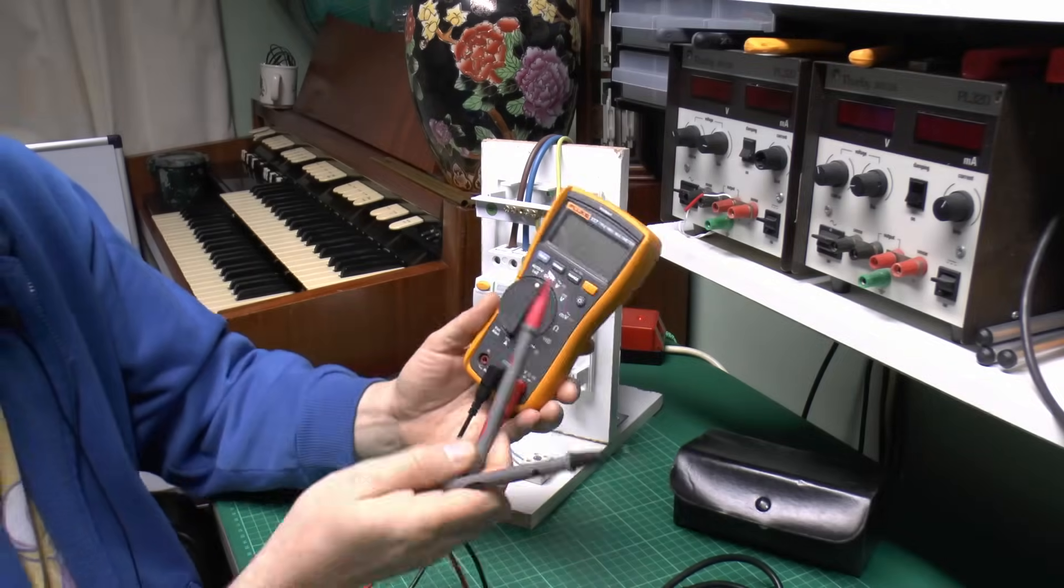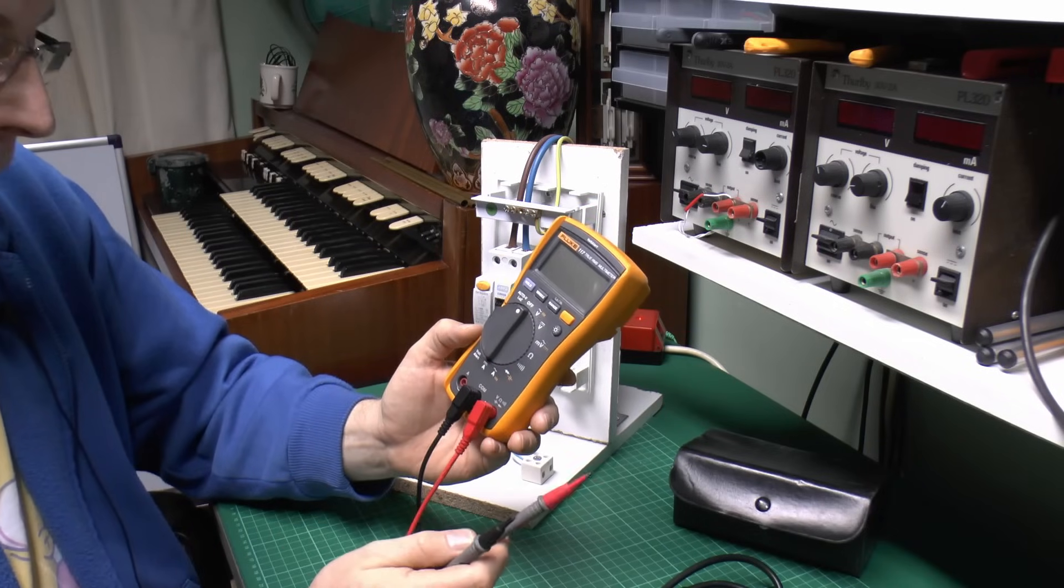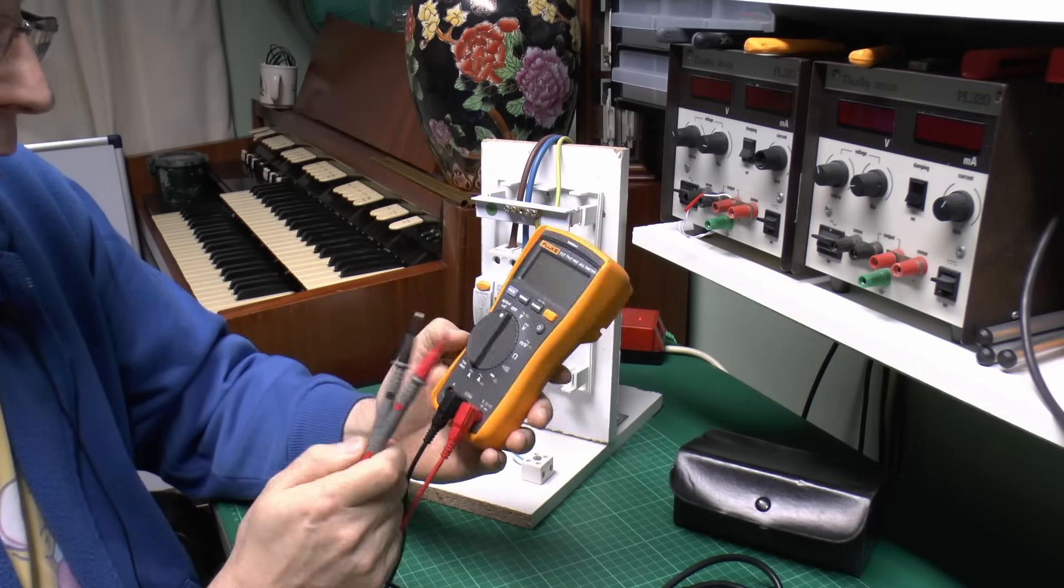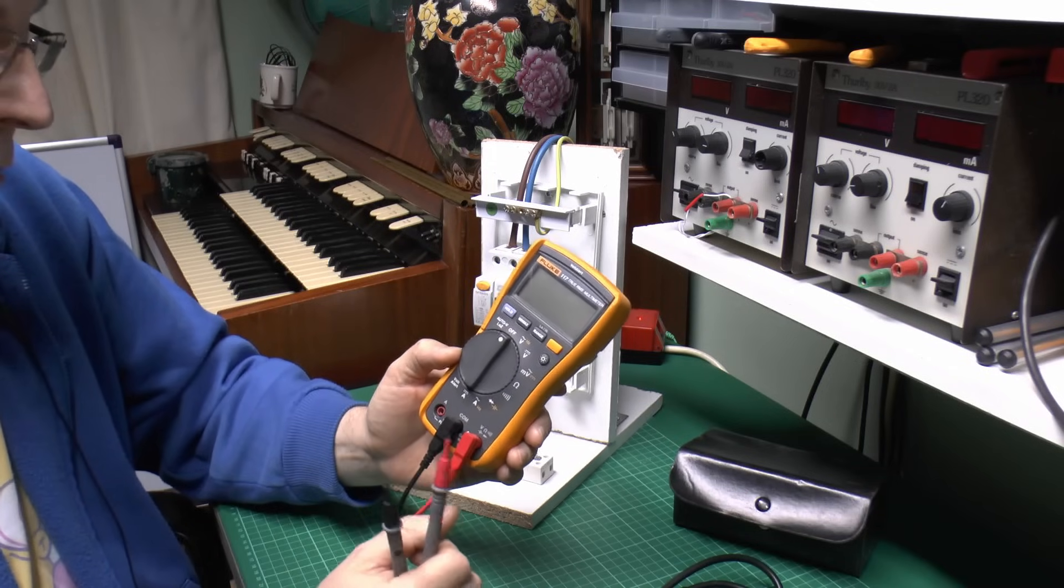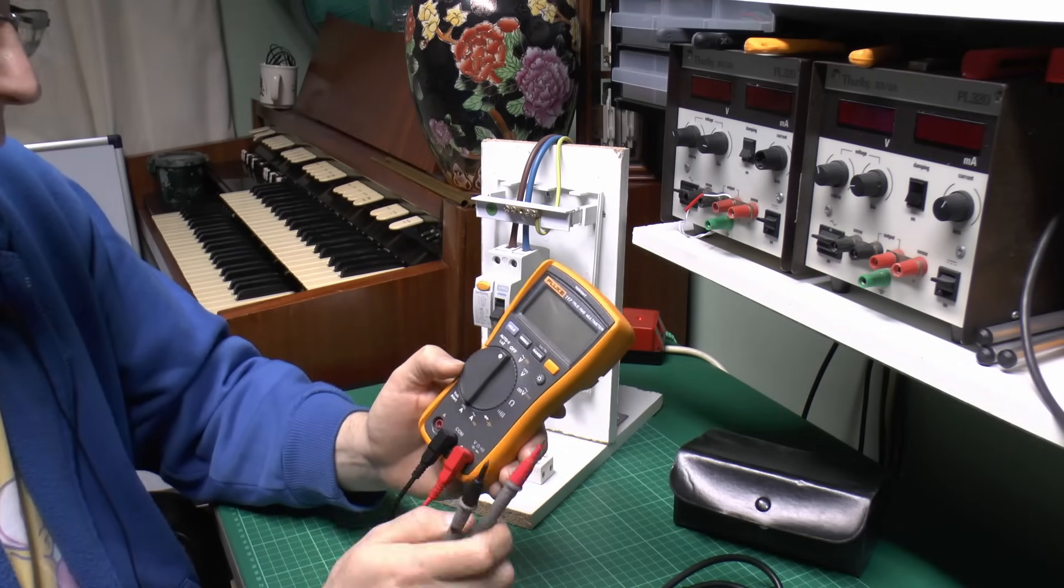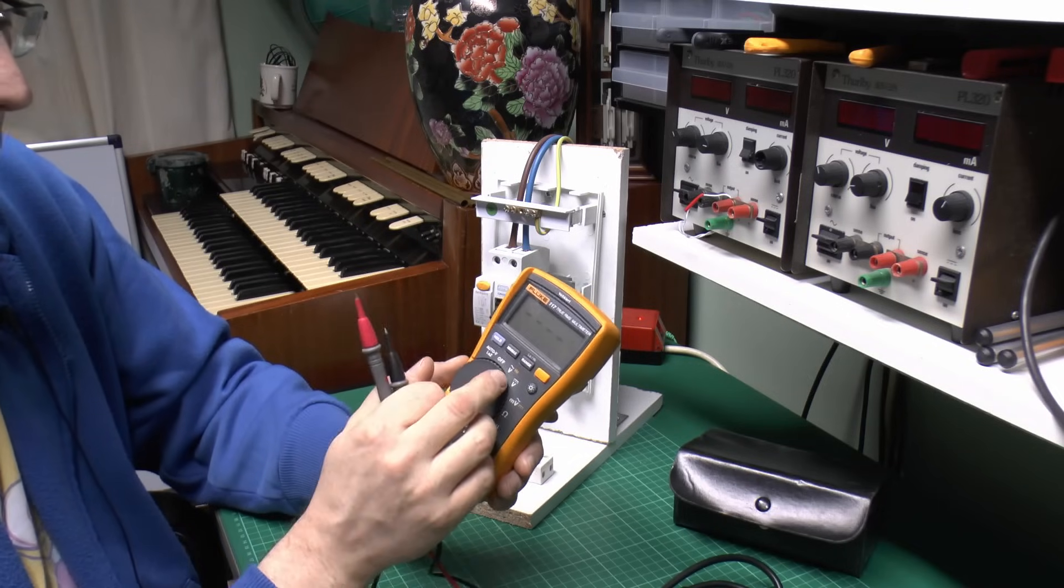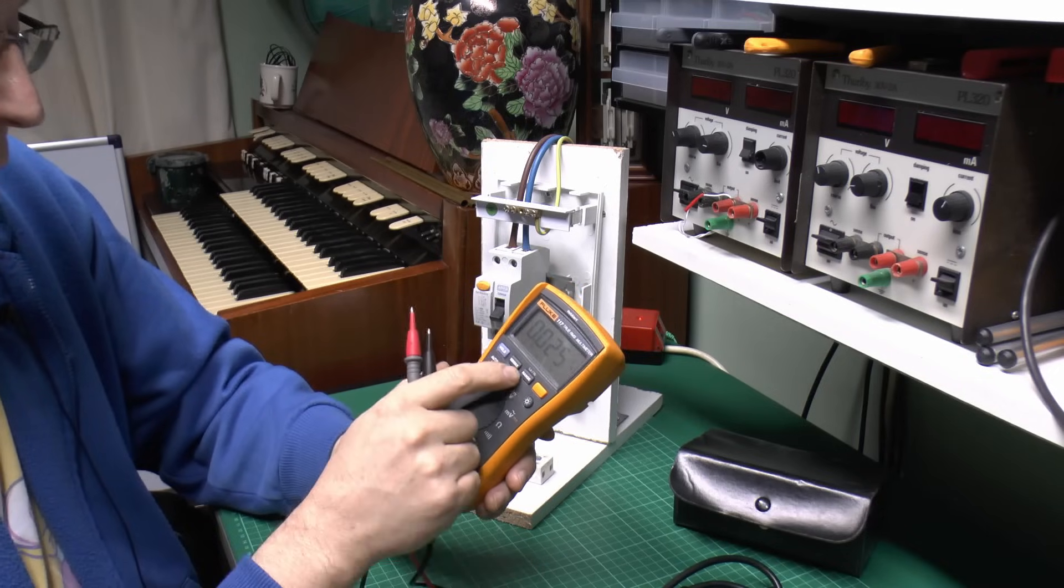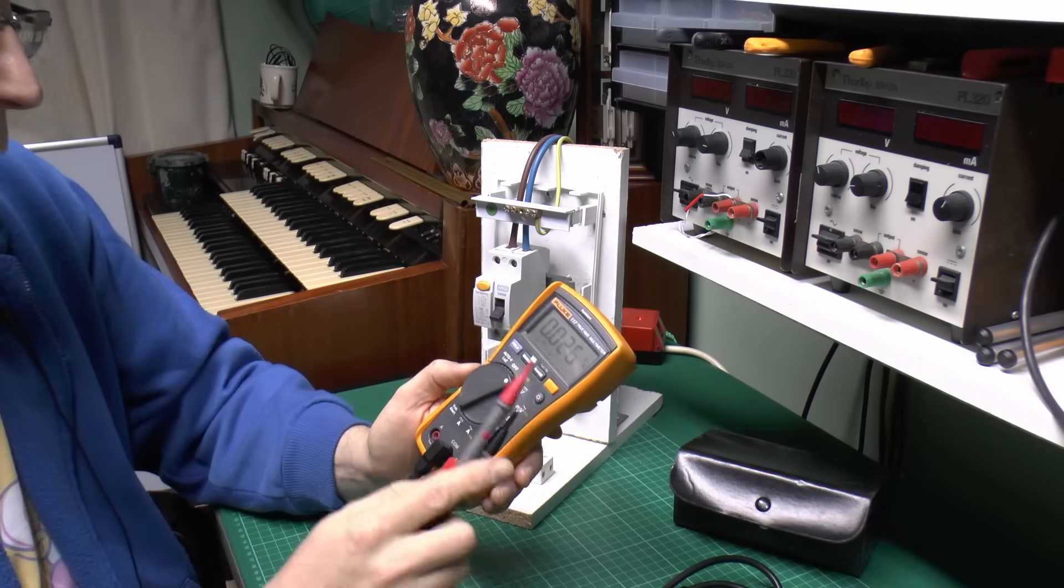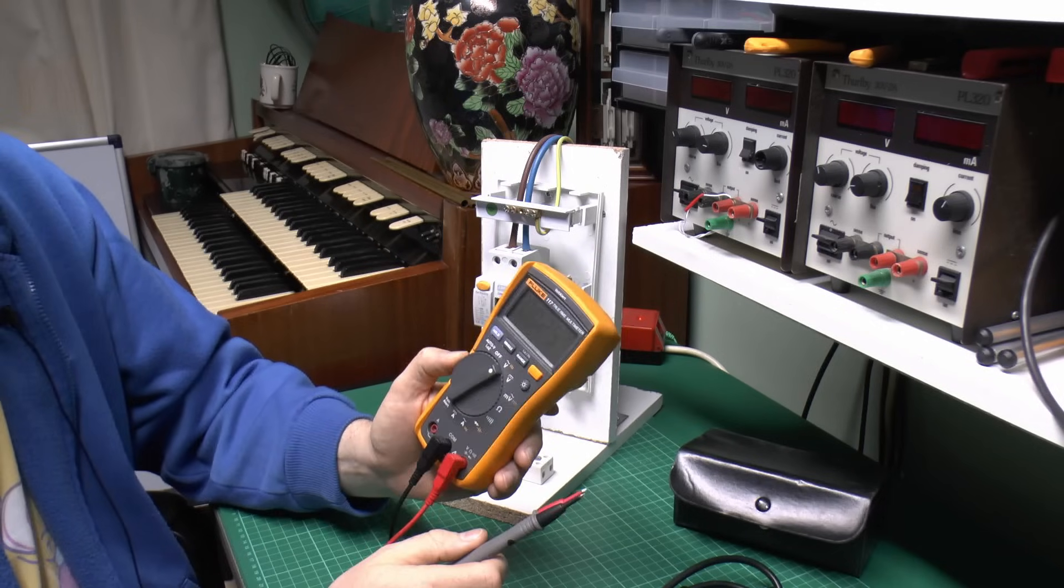Now something else you may have thought of using is a multimeter, and of course this does have the two test probes here which will connect to the actual circuit. And whilst of course these will display voltages, there is a possible problem in using these to prove that the power is disconnected, and the problem is that multimeters by their actual design have a variety of different sockets to plug the leads in. This particular one has three but others may have four, so you could actually plug things into the wrong holes and get the incorrect kind of readings. And of course they have a whole range of different settings here, and if you selected the wrong one of course and then just tried to test the voltage, all kinds of strange things may be displayed or in some cases nothing at all.